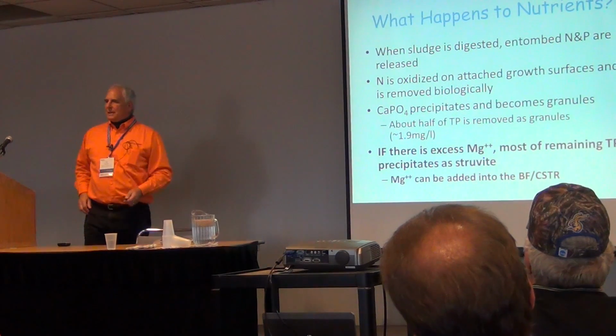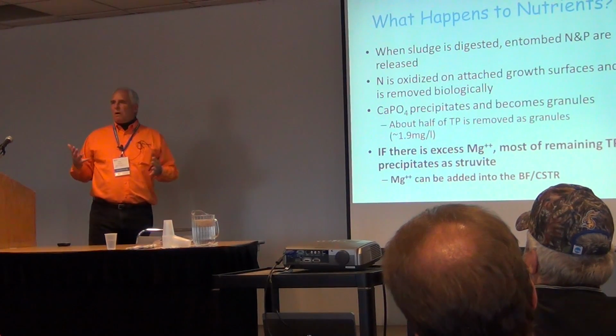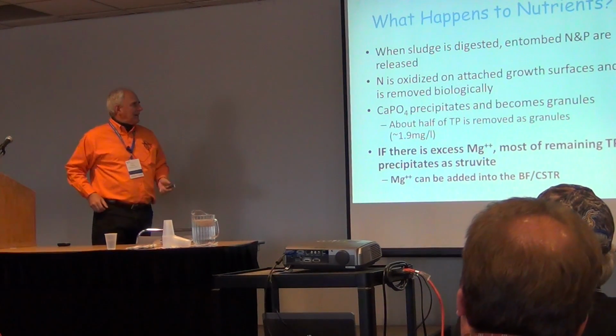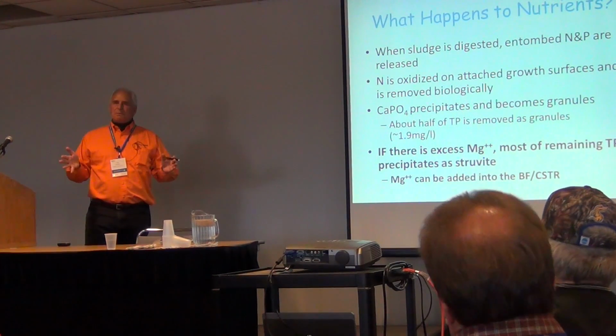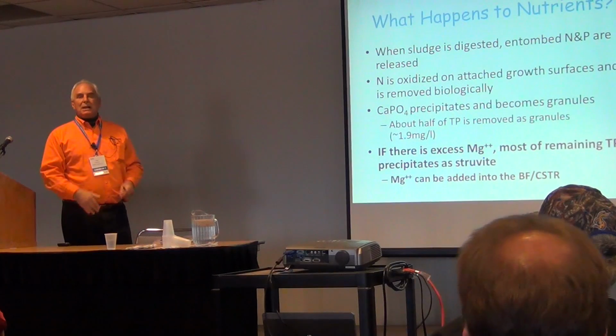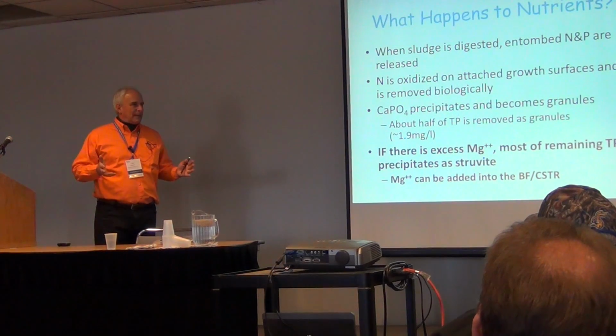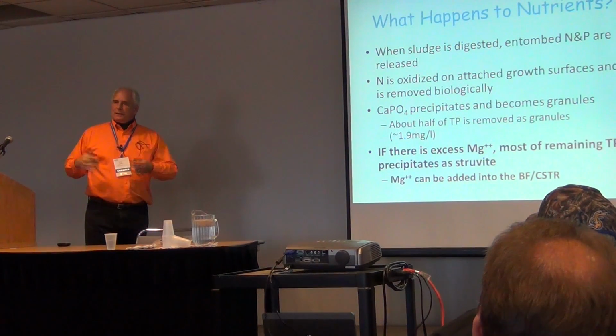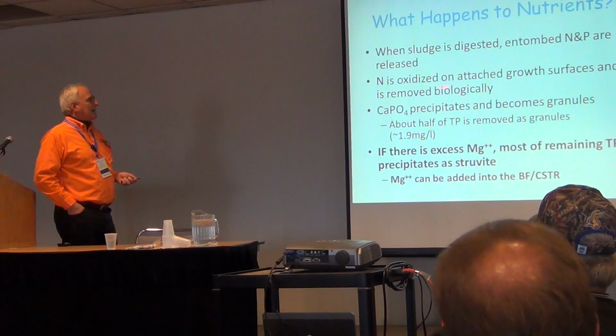All right, so what happens to nutrients? That's something that might be important here in Minnesota. But when sludge is digested, that is a reservoir for nitrogen and phosphorus, and that gets released. So you have to deal with that. And the nitrogen can be removed biologically. That's easy. Because we have our water going parallel to the surface, not across, we self-clean. So the grazers that I talked about, the worms and the larvae, are our self-cleaning mechanism. That's like continuously scraping your filter, and then turning the hard-to-settle suspended solids into heavy, dense worm castings. And so we get rid of the nitrogen that way.